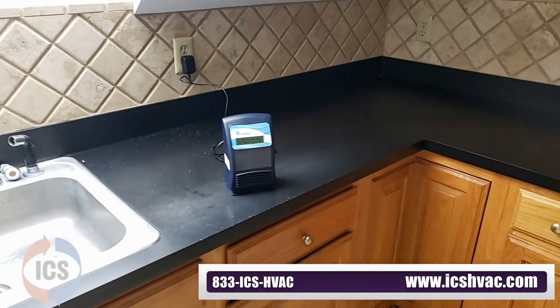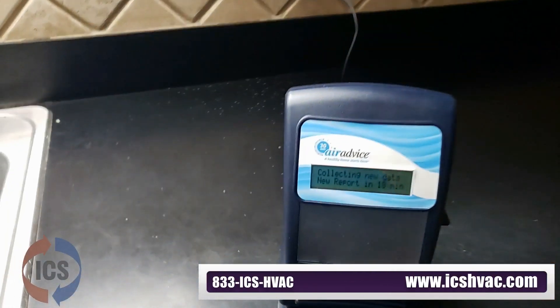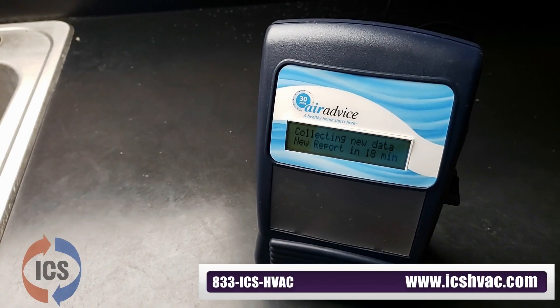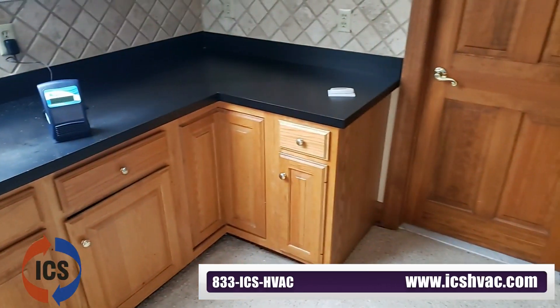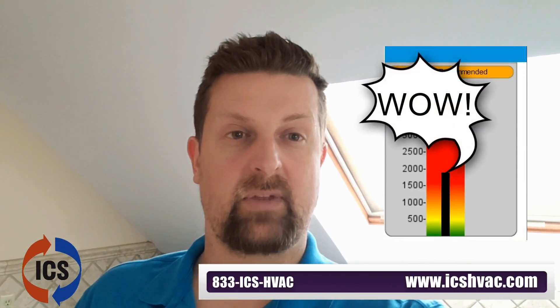This place is vacant but it is full of carpet. It's also over a garage space, so my nose has definitely picked up on this strong smell. We were backed up by an air monitor that we've had here for a couple of days, which has confirmed a high level of VOCs — volatile organic compounds. That's exactly what I'm smelling: the off-gassing of various chemicals, extremely strong. The report we're going to pull up shows VOC levels too high for human comfort — not healthy, not pleasant.